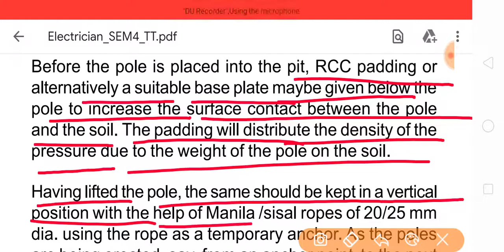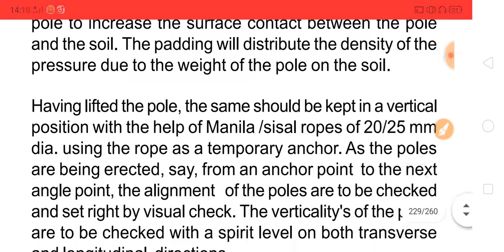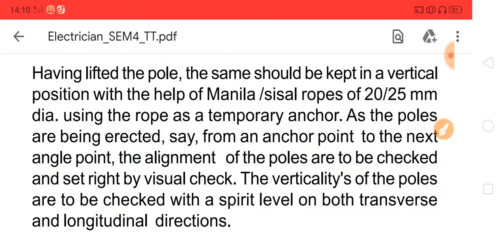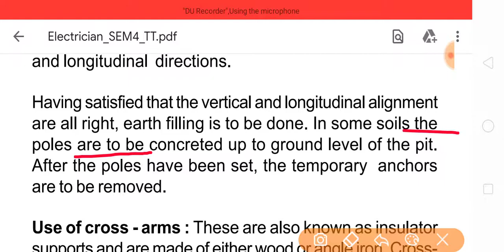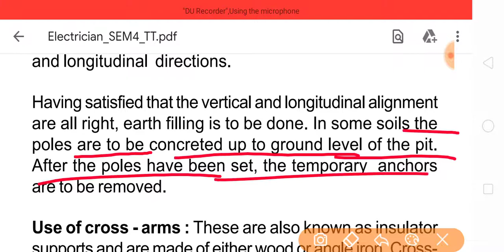Having lifted the pole, it should be kept in a vertical position with the help of Manila sisal ropes of 20-25 mm diameter. Use the ropes as temporary anchors as the poles are being erected, say from an anchor point to the next angle point. Alignment of the poles is to be checked and set right by visual check. The verticality of the pole is to be checked with a spirit level in both the transverse and longitudinal direction. Having satisfied that the vertical and longitudinal alignment are right, earth filling is to be done. In some soils, the poles are to be concreted up to ground level of the pit. After the poles have been set, the temporary anchors are to be removed.